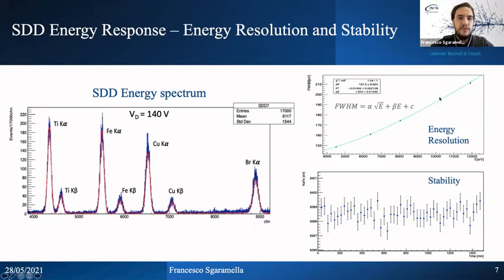The energy resolution is proportional to the square root of the energy, of course, plus a contribution due to the electronic noise. Regarding the stability, the values are fluctuating around the reference value of the K alpha iron. So in this case, at 140 volt, the energy response of the system is linear within a few electron volts. The energy resolution is fine and the system is stable.